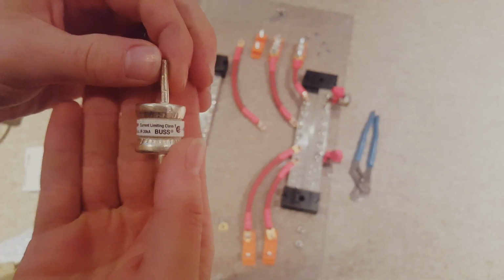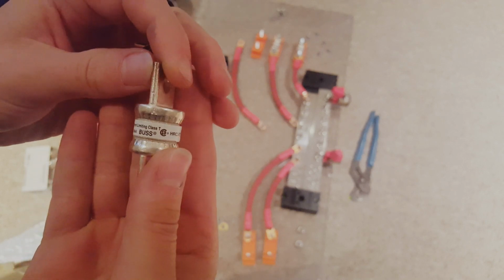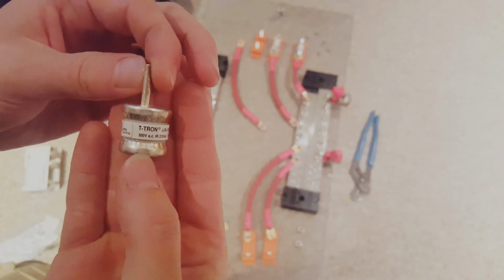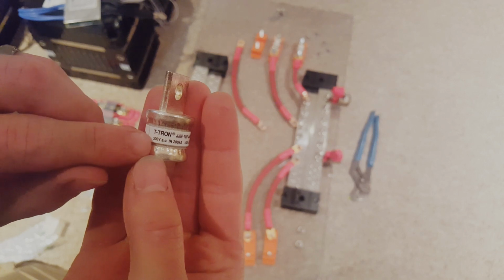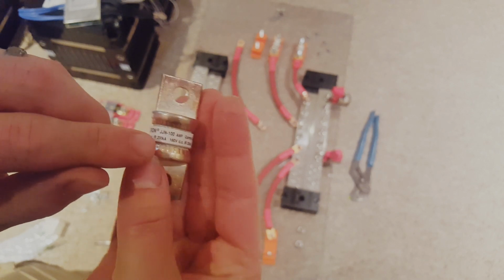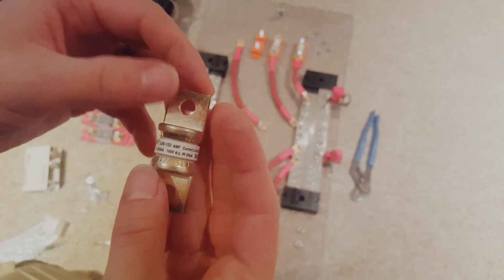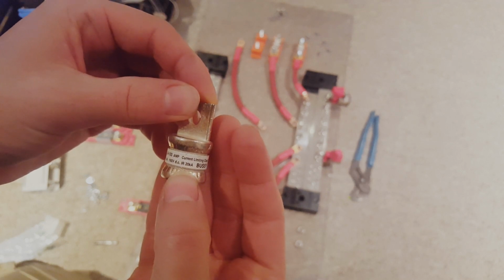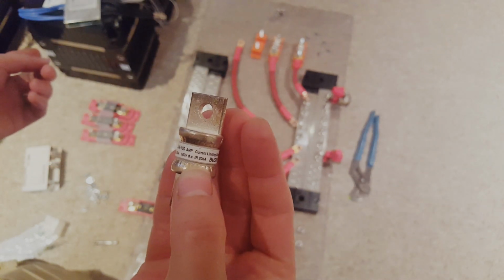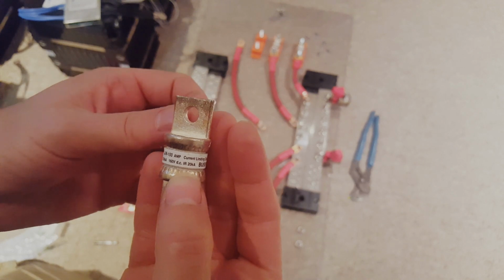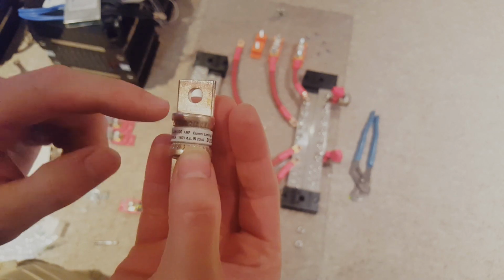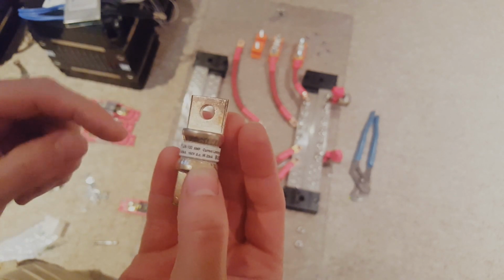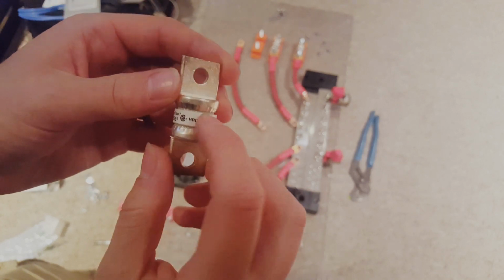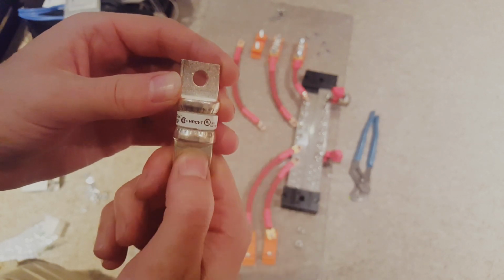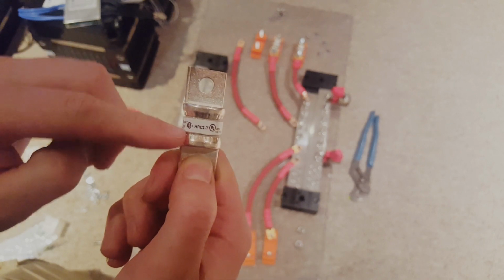So I bought these. These are bus current limiting Class T fuses. This particular one is rated to 300 volts AC and 160 volts DC, and the interruption rating is 20,000 amps. So if we have a dead short on these batteries, there's going to be a ton of current flowing through these, thousands of amps, I'm sure. And these are rated to interrupt that current, so I won't have to worry about any kind of arcing. Typically these have like a silica in here that will quench the arc if there is one established across here.